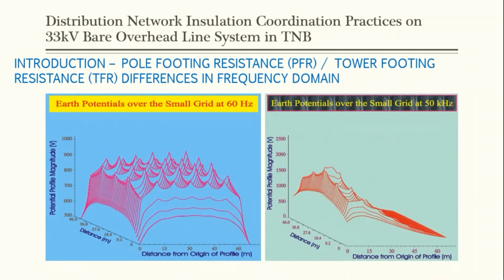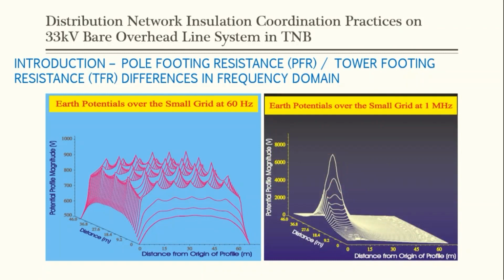And also, when we do some analysis in the frequency domain, the earth potential of a small grid at 60 hertz seems to have a uniform rise of earth potential. But the earth potential over the small grid at 50 kilohertz is different. Well, not a bit different, it's different, right? So you can see that it is concentrated at where the injection of current is being done. So the peak is where you have the current being injected to the ground. And at 1 megahertz it is even different. So at fault current, maybe the rise of earth potential will be uniform at different points. But lightning overvoltage can occur at a very high frequency, so the rise of earth potential will be different, right? So this is something that we have to bear in mind.